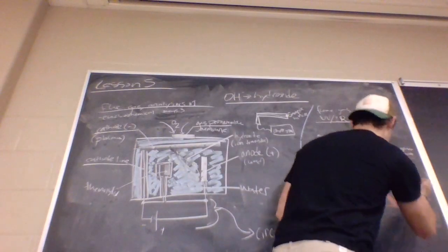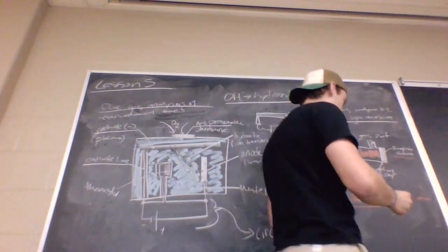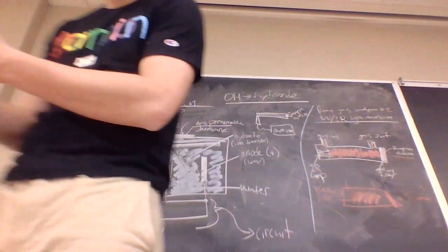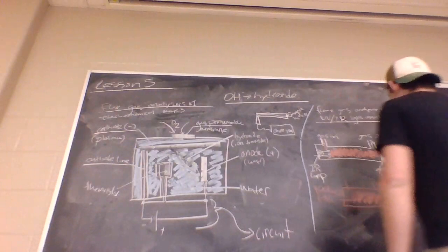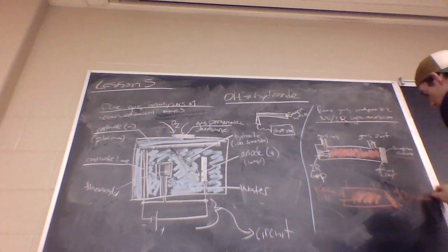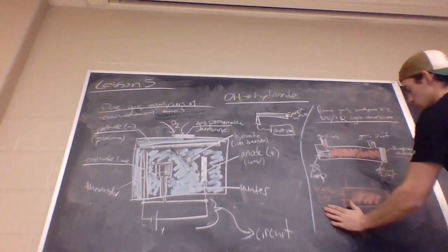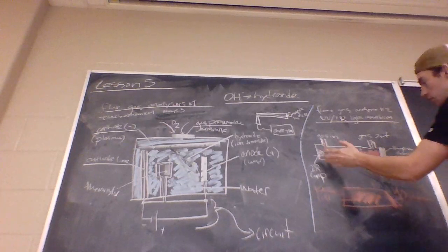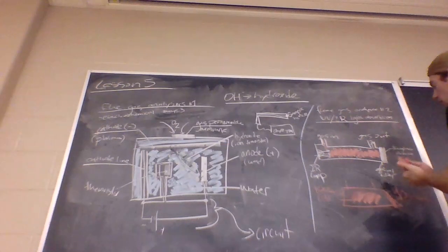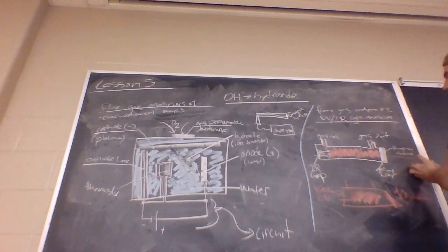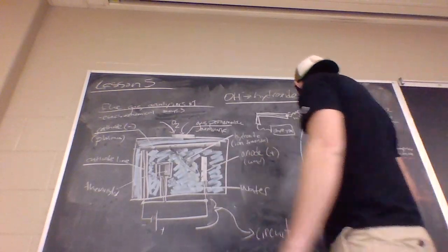So in this case, right now we have some gas going through. Usually it's most commonly used for carbon dioxide. And maybe now we get, let's say, 90 units of radiation. So it's detecting that change. We started out with a certain set value of radiation that the IR lamp is producing, but because the gas is absorbing it, it's not going to be detected as well by the thermopile detector because that radiation has left. So that's how this one works.